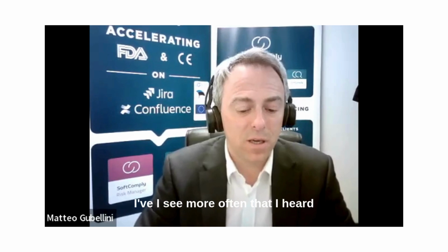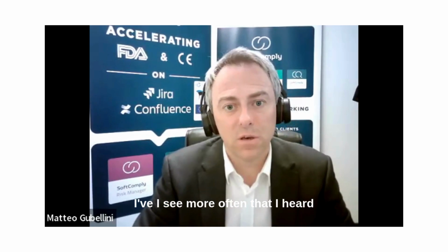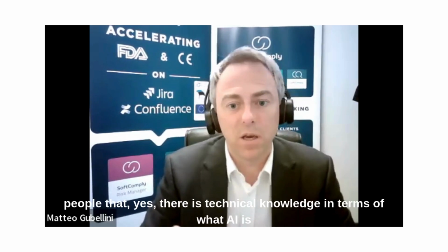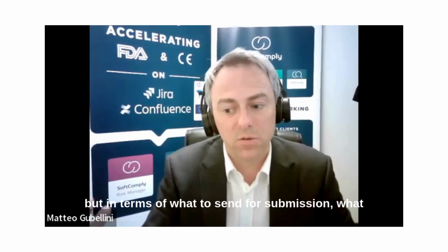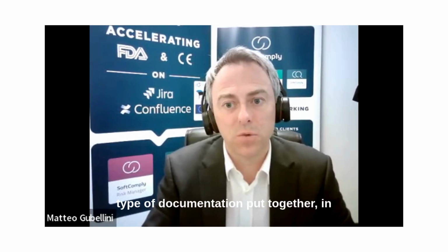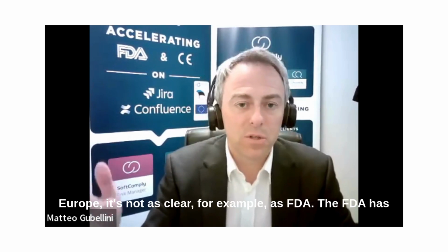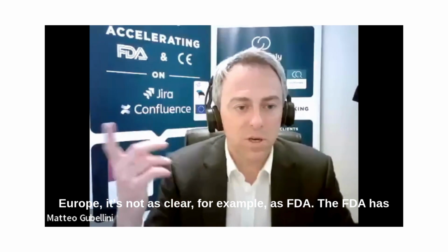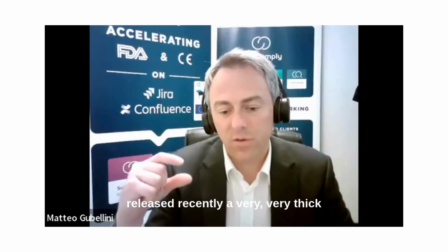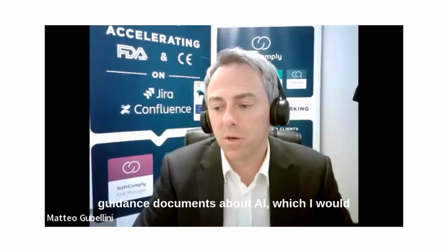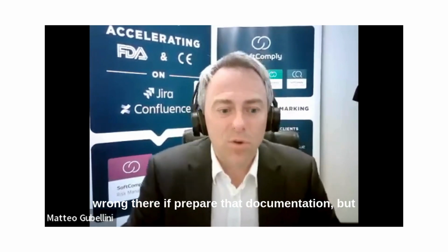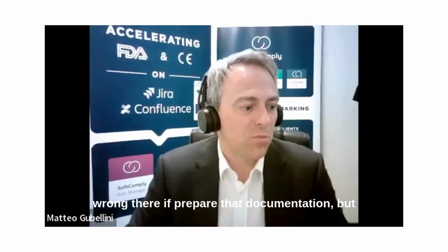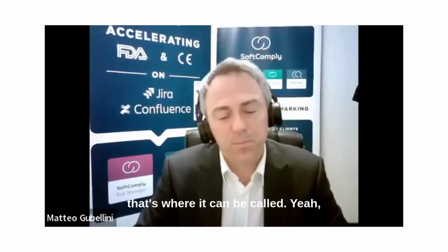So these are the aspects that I see more often. People say that yes, there is technical knowledge in terms of what AI is, but in terms of what to send for submission and what type of documentation to put together, in Europe it is not as clear as, for example, with the FDA. The FDA has recently released a very, very thick guidance document about AI, which I would suggest following anyway, because there's nothing really wrong there if you prepare that documentation, but that's where you can be caught.